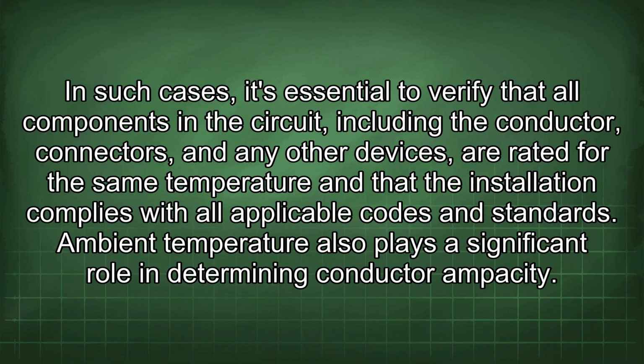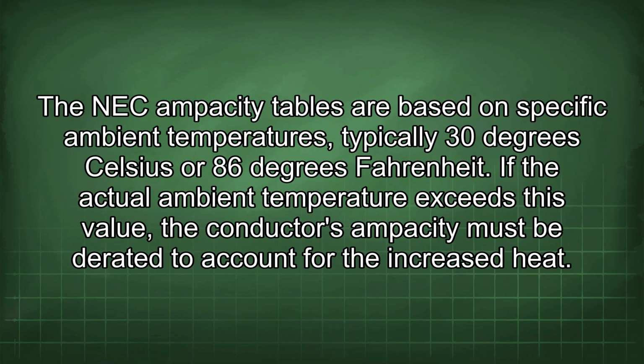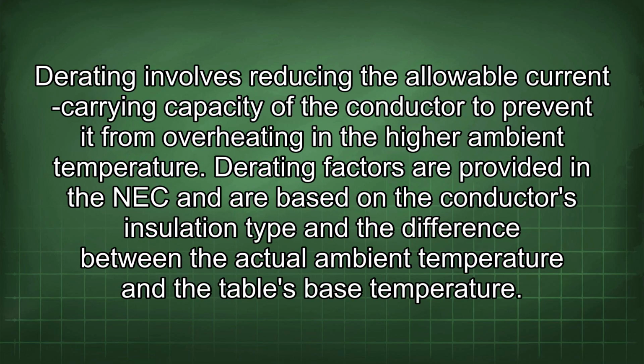Ambient temperature also plays a significant role in determining conductor ampacity. The NEC ampacity tables are based on specific ambient temperatures, typically 30 degrees Celsius or 86 degrees Fahrenheit. If the actual ambient temperature exceeds this value, the conductor's ampacity must be derated to account for the increased heat. Derating involves reducing the allowable current carrying capacity of the conductor to prevent it from overheating in a high ambient temperature. Derating factors are provided in the NEC and are based on the conductor's insulation type and the difference between the actual ambient temperature and the table's base temperature.